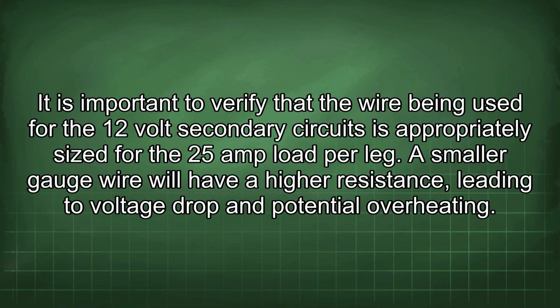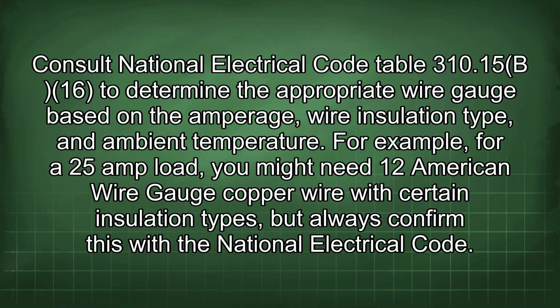It is important to verify that the wire being used for the 12-volt secondary circuits is appropriately sized for the 25 amp load per leg. A smaller gauge wire will have a higher resistance, leading to voltage drop and potential overheating. Consult National Electrical Code Table 310.15(B)(16) to determine the appropriate wire gauge based on the amperage, wire insulation type, and ambient temperature. For example, for a 25 amp load, you might need 12 American wire gauge copper wire with certain insulation types, but always confirm this with the National Electrical Code.